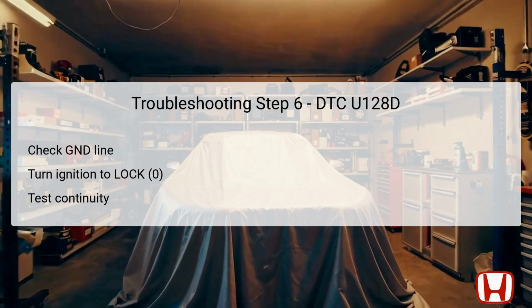Testing for continuity in this manner will indicate whether the ground path is intact. If continuity is confirmed, this suggests that the ground line is functional. However, failure to establish continuity points to an open circuit or high resistance within the ground wiring, which needs to be repaired to restore proper communication and module functionality.